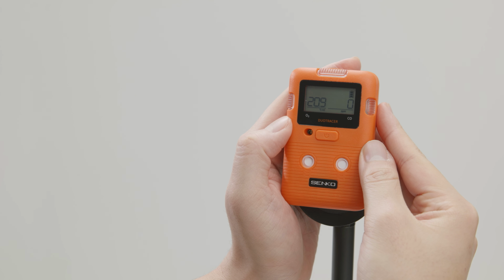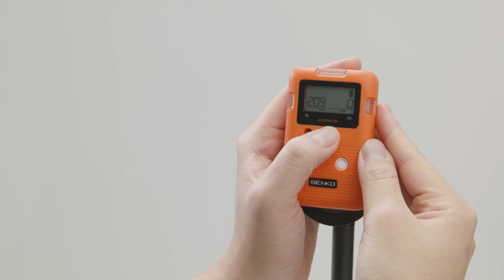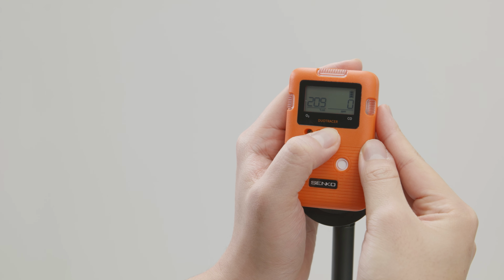Duo Tracer uses an intuitive, single-button menu structure, so while you're in measurement mode, each short press of the button moves the screen to the next menu item. You can scroll through information such as minimum/maximum values, as well as STEL and TWA, calibration interval, alarm set points, firmware version, and gas-specific correction concentration information.